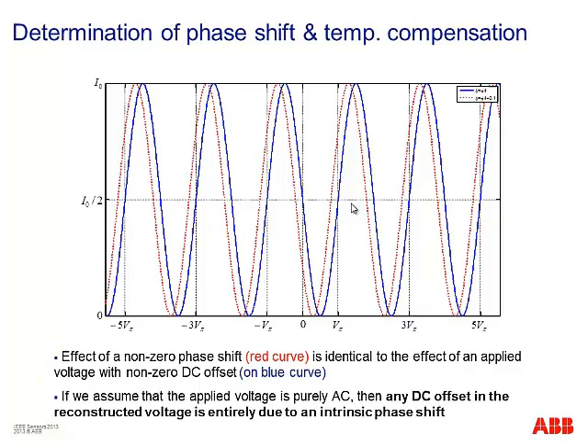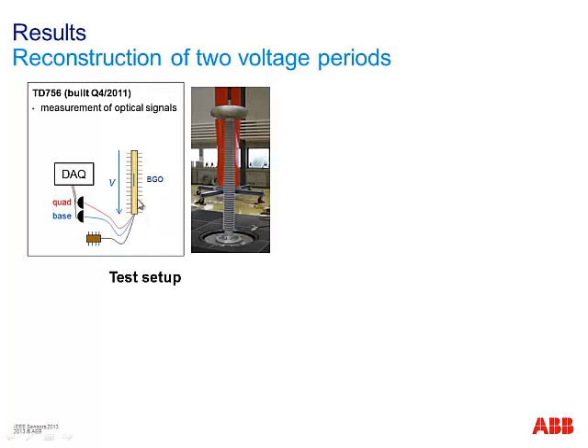Of course, we have verified this. This is the setup that we have used to verify it. So here we have a prototype of our actual voltage sensor. The BGO crystal would be a very small thing here in the middle. The BGO crystal only has a length of 30 centimeter. The whole device here is 2 meters more or less in height. And we apply the rated voltage to this device. It has some insulation, of course. And then we have here a light source. We inject it. It's actually a mirrored configuration. So instead of going through with the light, we go to the mirror that is on top of the BGO, and we come back and go into our two detectors.